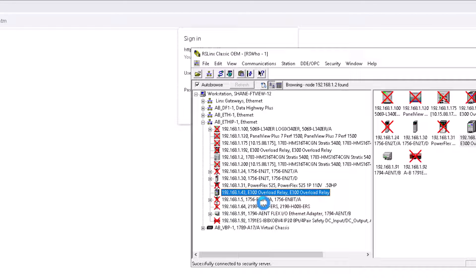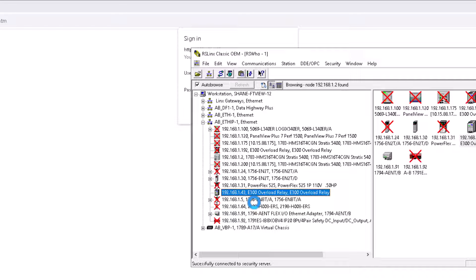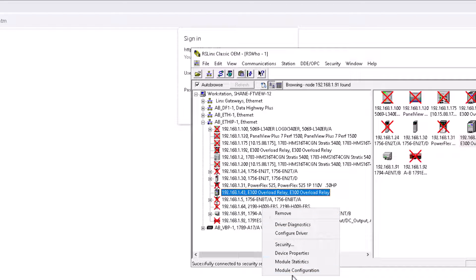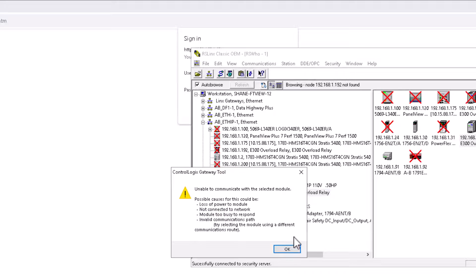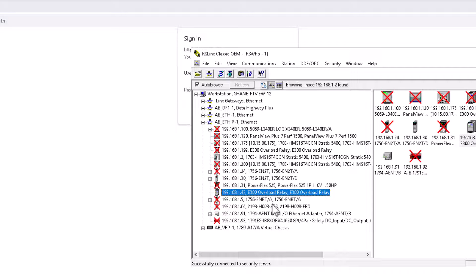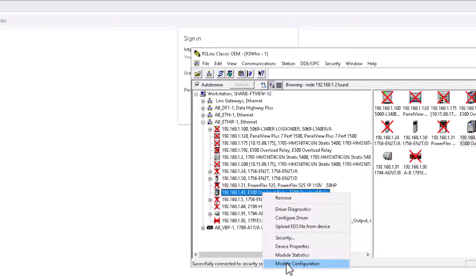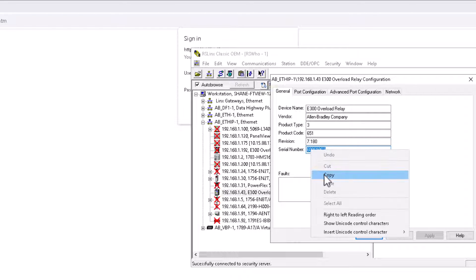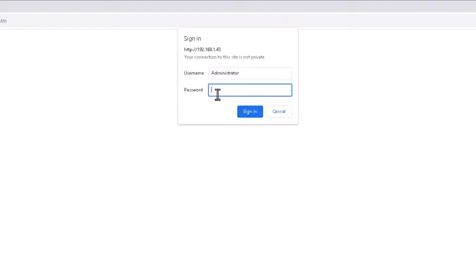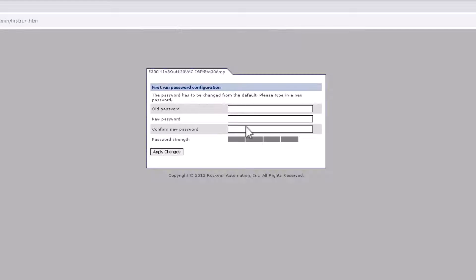Remember I said this is going to be the serial number. So we're going to open up RSLinx and we're going to go down to configuration. Now in configuration of RSLinx, you're going to see the actual serial number. So module configuration, and then as soon as this opens, we're going to go ahead and grab that serial number. For some reason it did not pull it up. So let's open it up again. We're going to grab the serial number right here, paste it in here, and this will give you access.